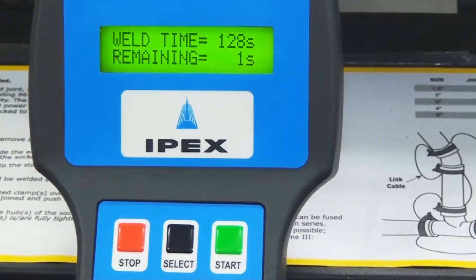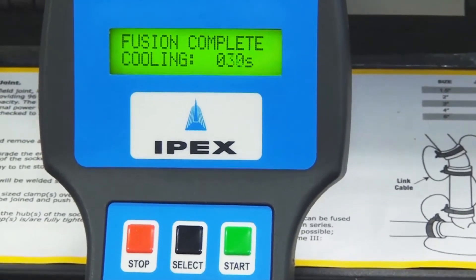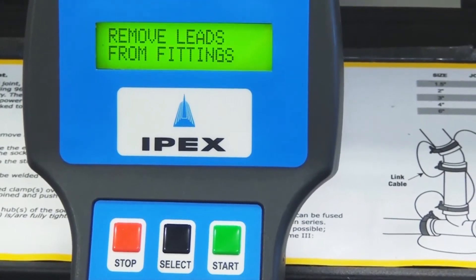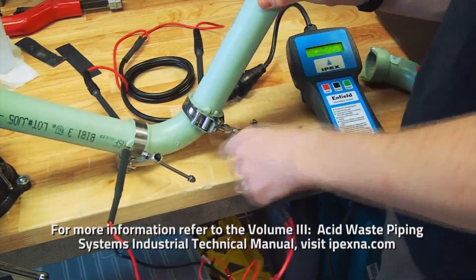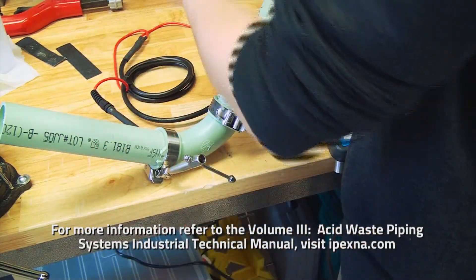Upon completion of the fusion cycle, an audible alarm will sound and the message 'fusion complete' will be displayed. A 30-second rest period must be observed to allow the joints to cool before disconnecting the leads. The fusion machine will automatically reset, ready for the next operation. Allow 5 additional minutes before removing the clamps so that the joint can sufficiently cool and properly cure.